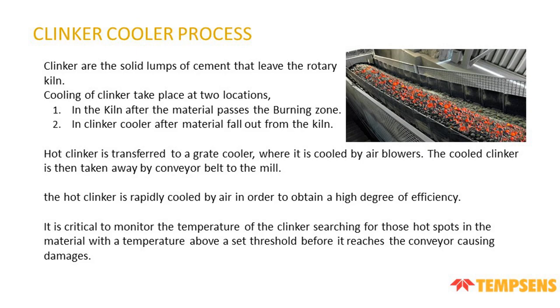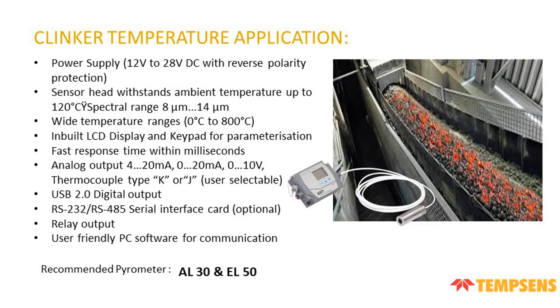Clinker temperature application. We offer EL30 and EL50. EL50 is widely used in a cement plant. EL50 has two different sides. One side is the sensor head and the other side is the electronics. The sensor head withstands ambient temperatures up to 120 degrees centigrade. Wide temperature range, 0 to 800 degrees.